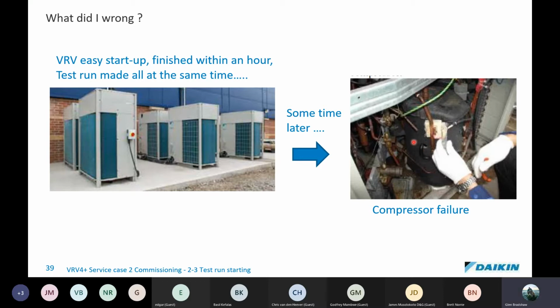I'm going to ask you guys out there: in a system like this, where there are 3 systems and you try to run them all up together, what could go wrong? Yeah, gas pipes swapped around. Good chance that he swapped these refrigerant pipes around. You're right. What else can be swapped around between these systems? Wiring, as well. So it's never a good idea on commissioning to try to run more than one system at a time. It's also very important that the service engineer keeps his eye on a system and monitors the operating parameters one at a time.